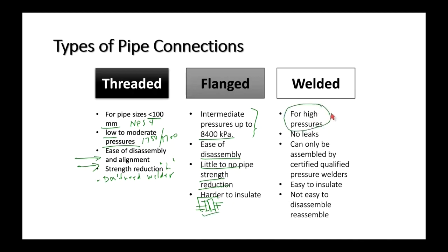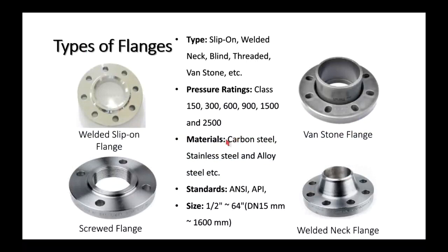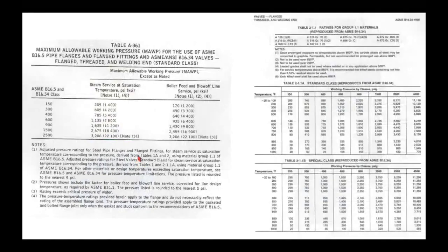The premium method of connecting pipe is welding — for very high pressures, it won't leak. However, you need certified qualified pressure welders and registered weld procedures. If you need to disassemble and reassemble, you'd use flanges. Types of flanges include: slip-on, Van Stone (loose), weld neck, and screwed-on flanges — though screwed-on flanges are not much better than threaded fittings since you still cut threads in the pipe.